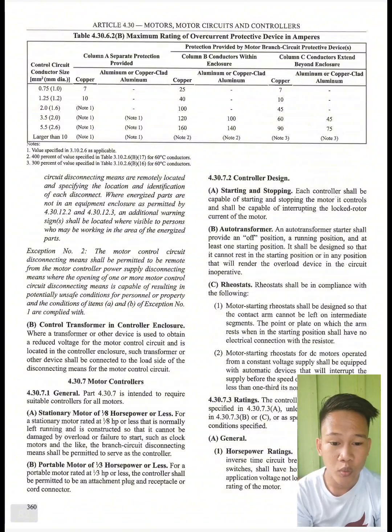Next is 3.5, so 2. The copper is also in note 1. The aluminum or copper clad aluminum is also in note 1. Then column B, 120. For aluminum or copper clad aluminum, 100. Then in column C, 60. Then for aluminum or copper clad aluminum, 45. Next is 5.5, 2.6. Note 1 again for the copper, and also for the aluminum. Column B is 160. Then for aluminum, 140. Then in column C, the copper is 90. Then the aluminum or copper clad aluminum, 75.